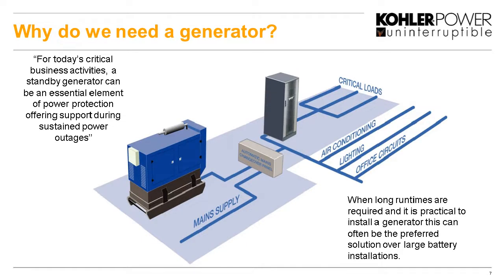So, when we look at why we need a generator, in today's business activities the long run time a generator provides has become the essential element. It is just not acceptable nowadays not to continue to operate even if the mains disappears. We have to be online 24/7. So a generator is very essential in making sure we can supply our customers with the service we provide. Typically for long run times we would put a generator in, and this is the preferred solution rather than a large battery installation, although, like I said, that is possible but not always preferred.